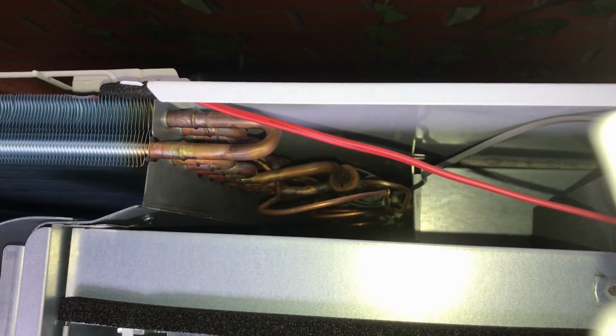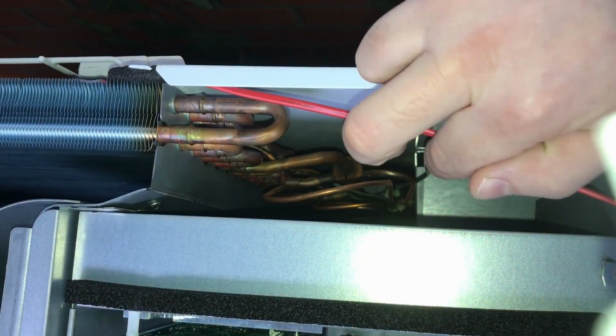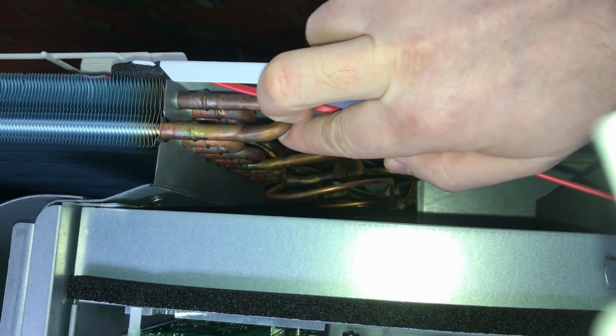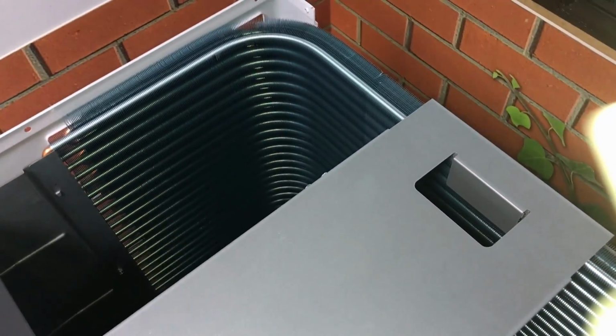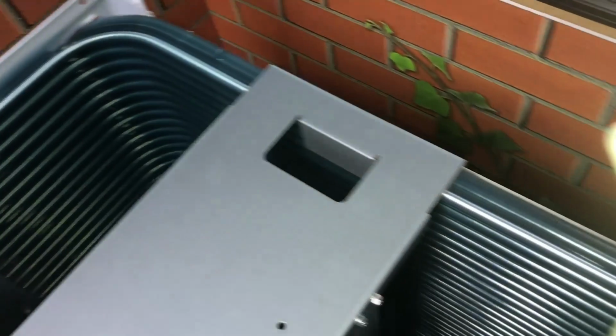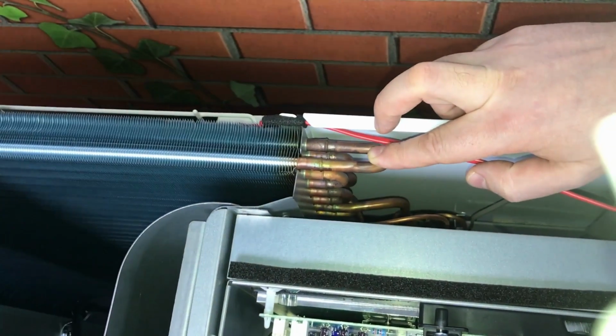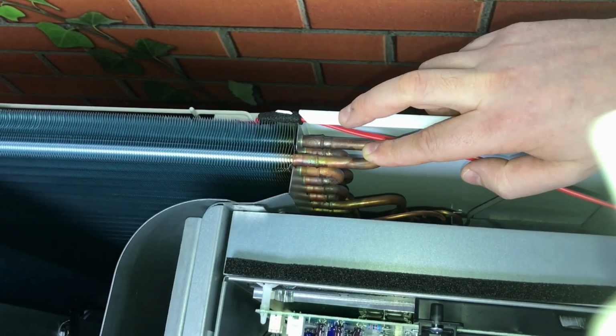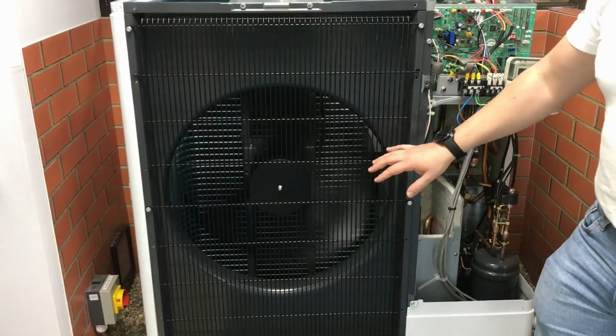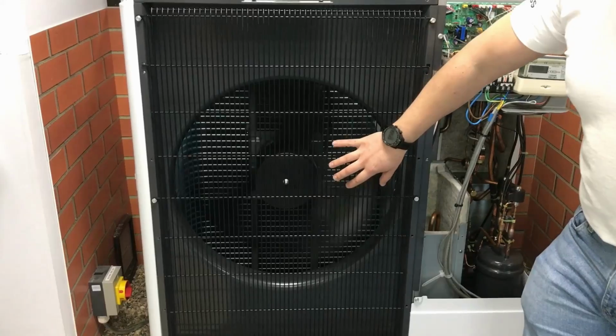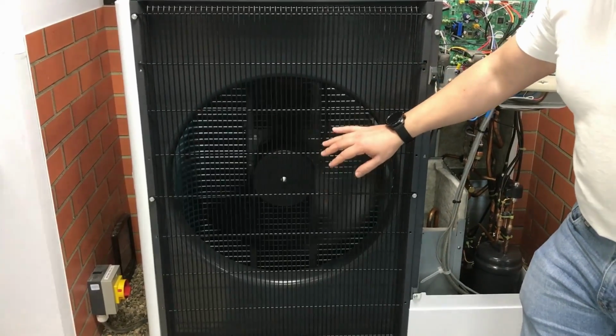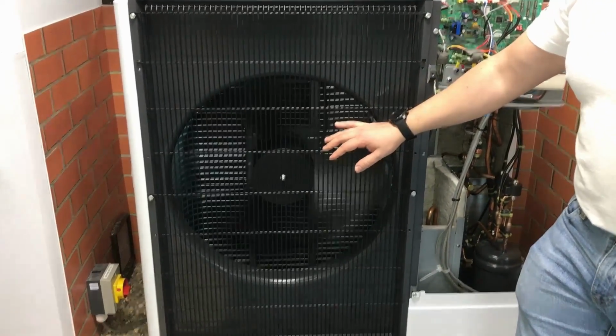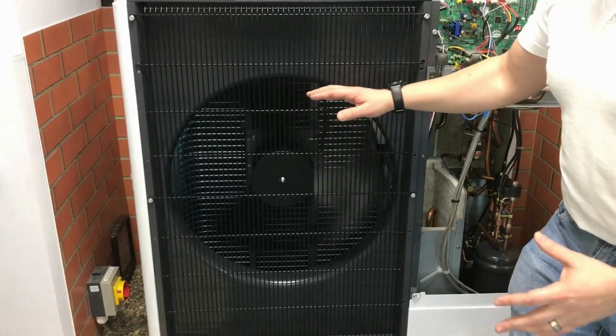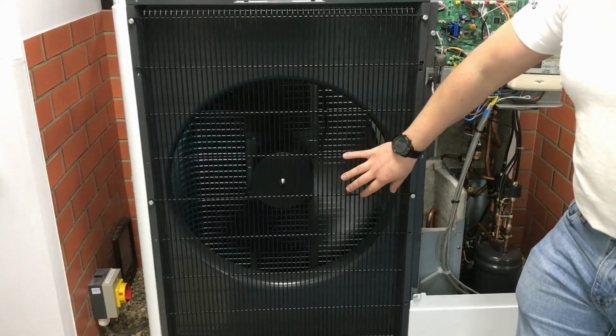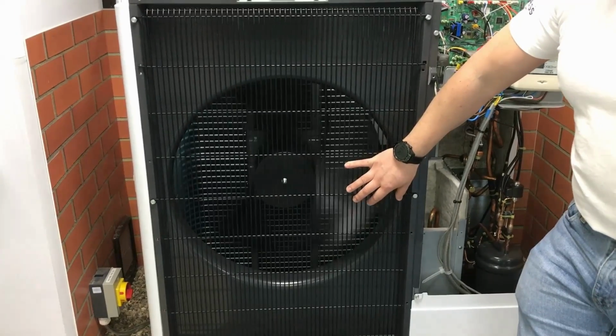So a mix of liquid and vapour passing from that pipework onto the manifold and loading up that coil. As the refrigerant passes through that coil, it's all going to go from being a mix of liquid and vapour to all being a vapour as we steal energy from the air around the unit. Got a fan here drawing the air across that coil, and that fan's going to be ramping itself up and down to suit the requirements for that coil to make sure it's all gone from being a liquid to all being a vapour, but thereby stealing that energy from the air around the unit.